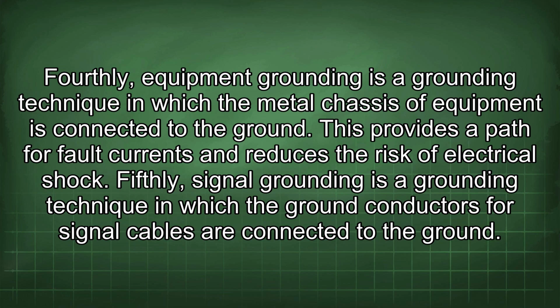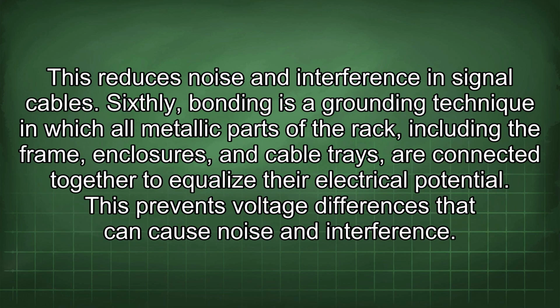Fifthly, signal grounding is a grounding technique in which the ground conductors for signal cables are connected to the ground. This reduces noise and interference in signal cables. Sixthly, bonding is a grounding technique in which all metallic parts of the rack, including the frame, enclosures, and cable trays, are connected together to equalize their electrical potential. This prevents voltage differences that can cause noise and interference.